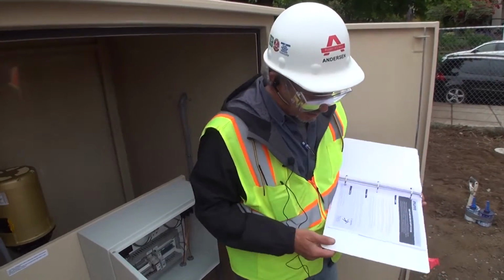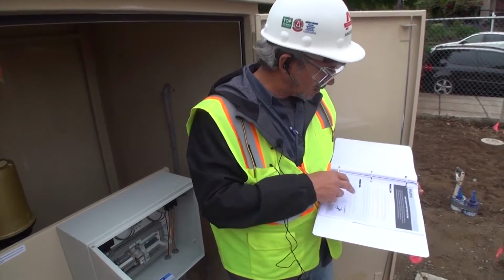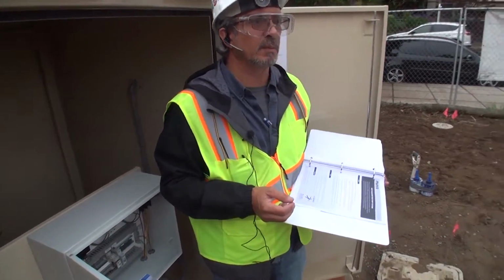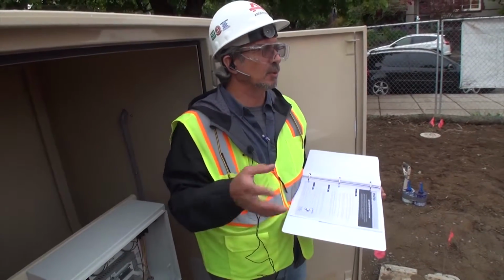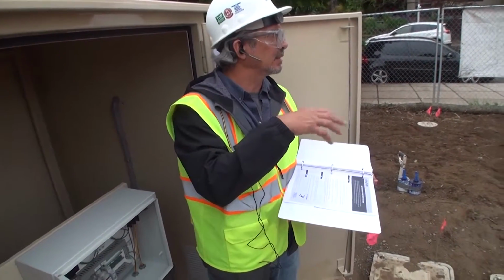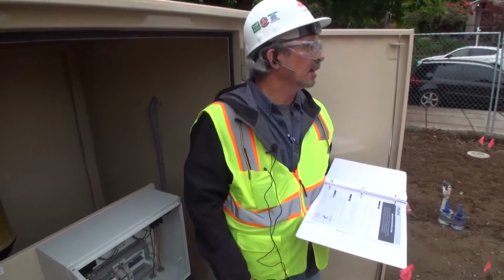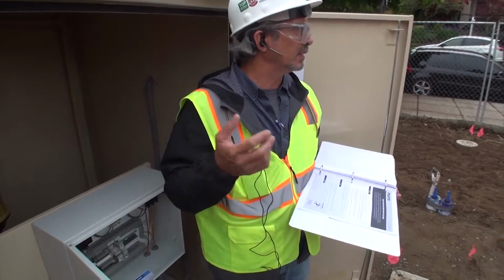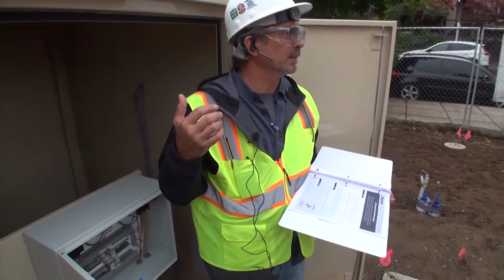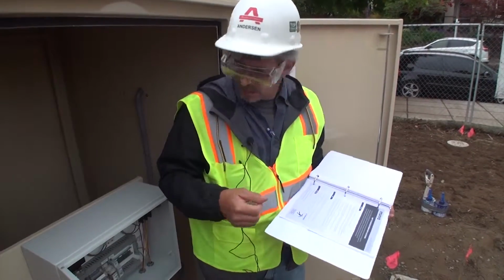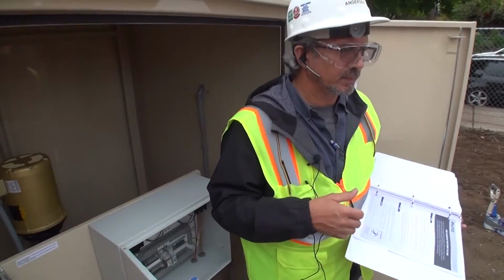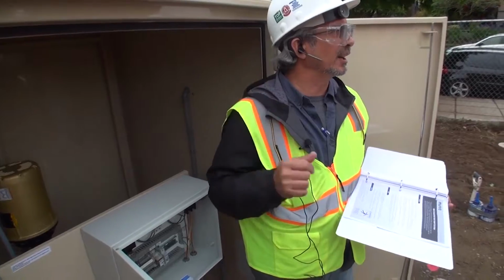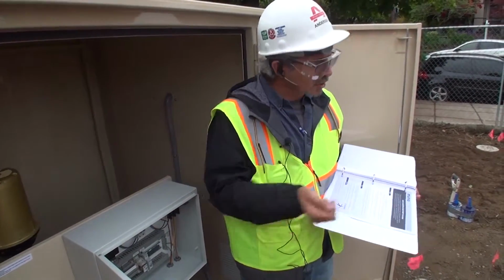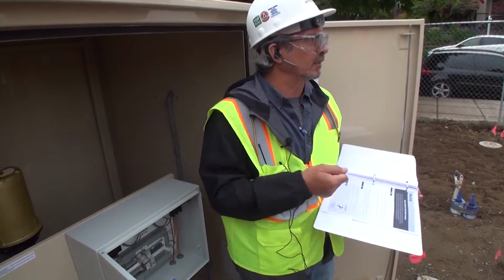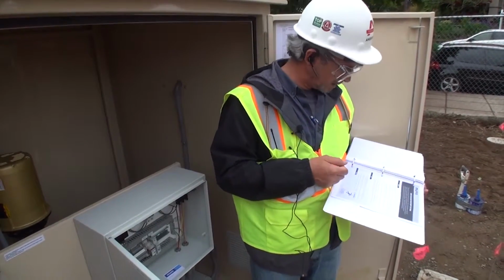The pump, it says exercise the valves, open and close fully multiple times. What happens is as your water is running through there, it's building up calcium and mineral deposits on the sealing surfaces, and you want these valves to hold when you need them. So maybe we should, I wish I could show you. I wish we were on the other side right now. I would show you. Just make sure you close them and open them a couple of times to wipe that surface. I would do that at least once a year.